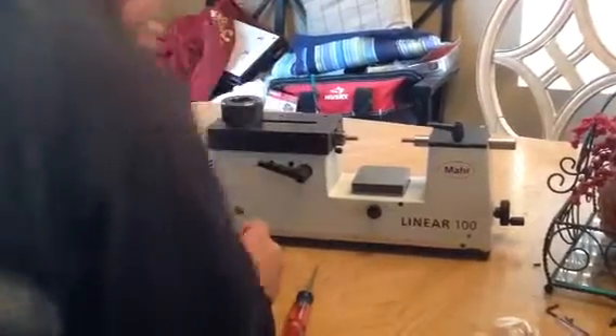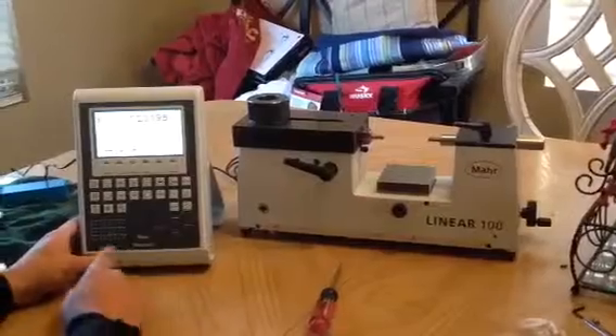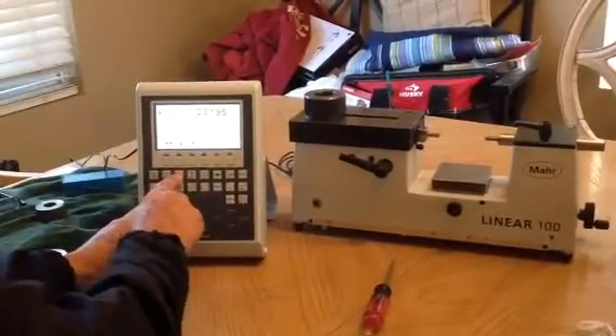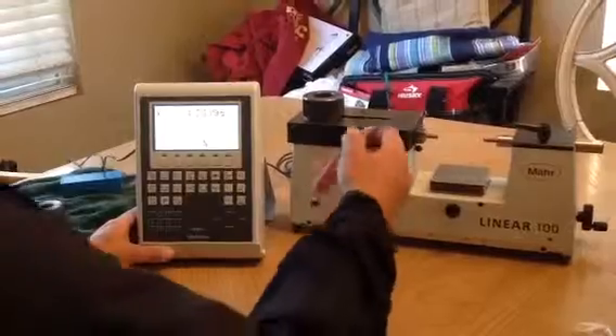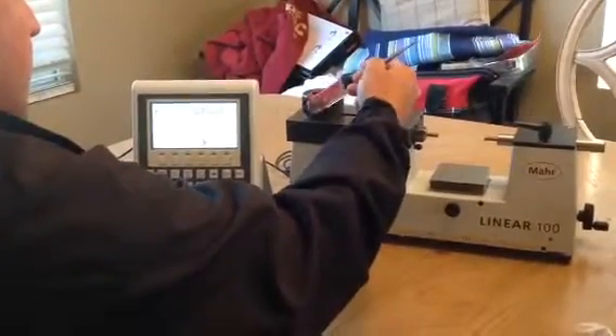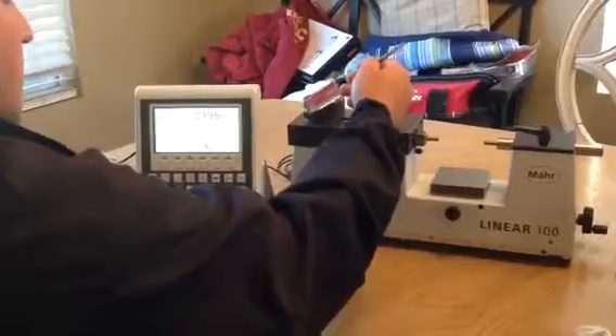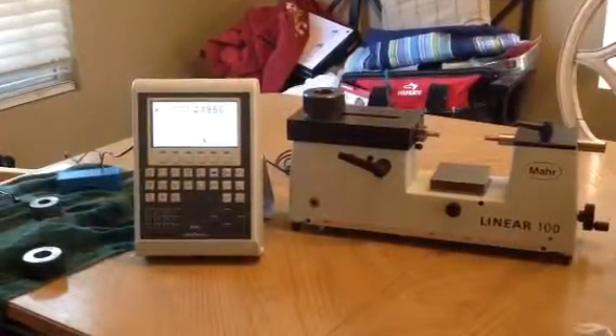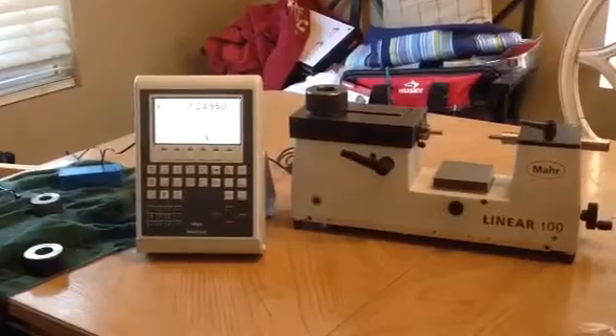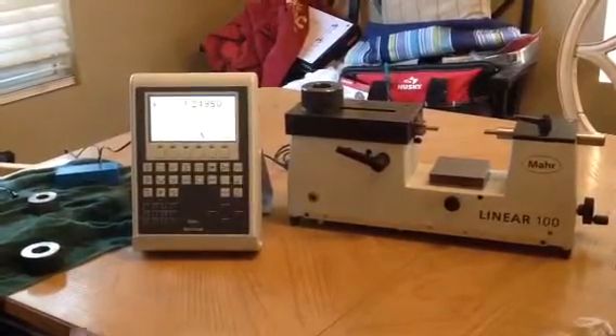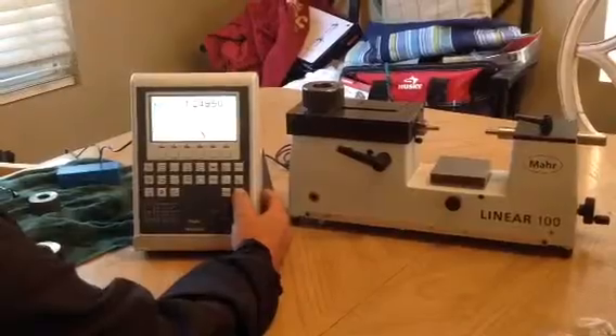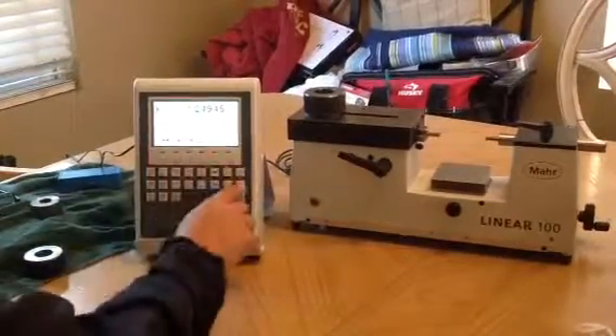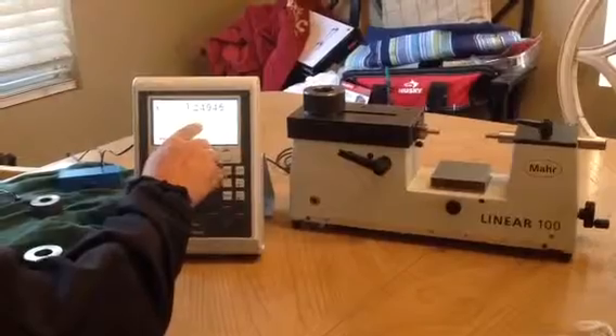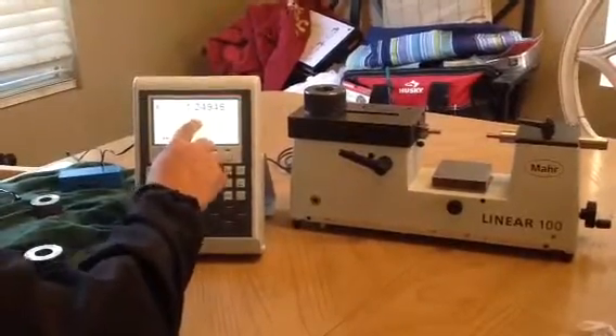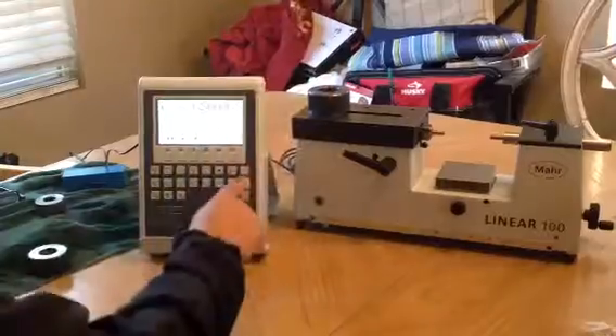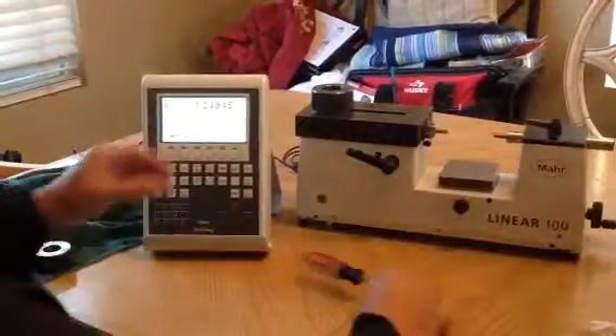Put it on here. And then I go to this button right here, which is to do a max. So I hit that. And then I tap my ring, and voila, there's my max, 1.2495. Pretty simple to do. If I want to collect the data, I can collect it by hitting this button. I know it's hard to see that number, but it says 1.2495 on my screen now. I can also hit the data send button, which will send it to your PC.